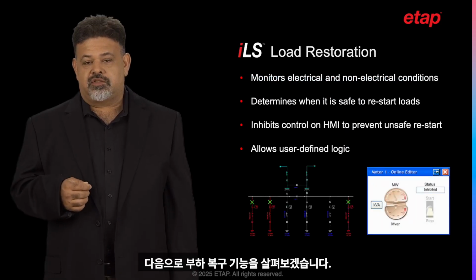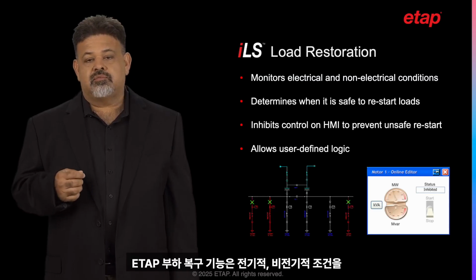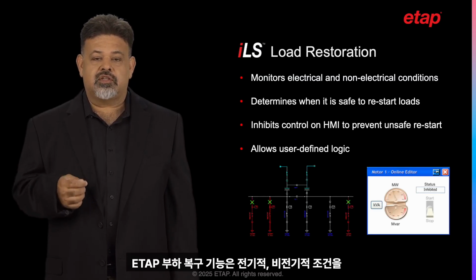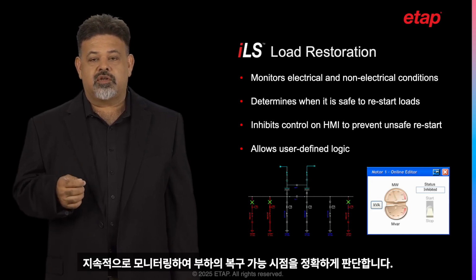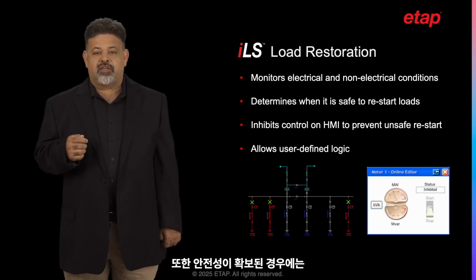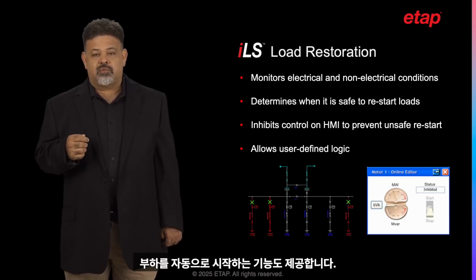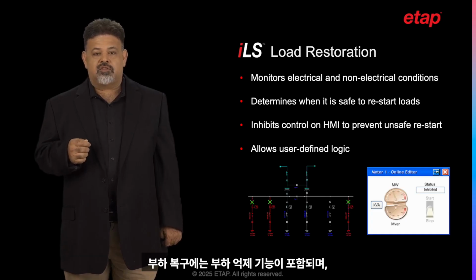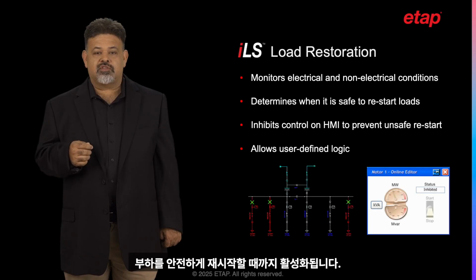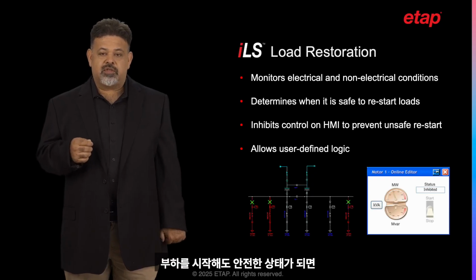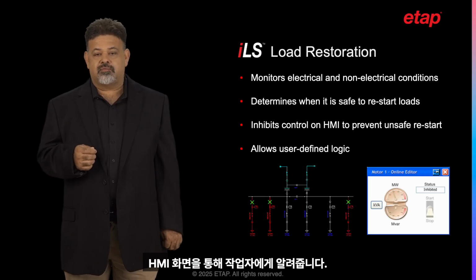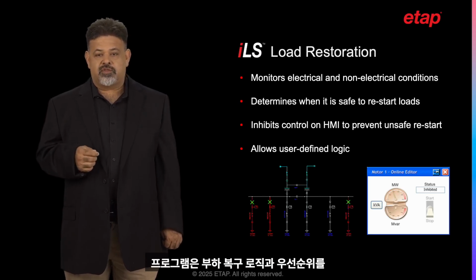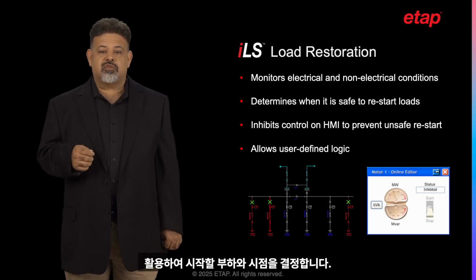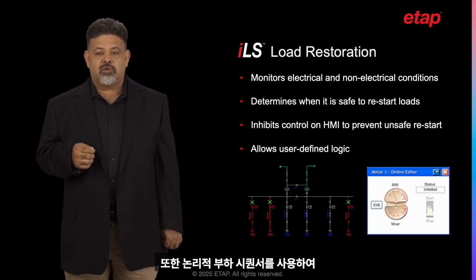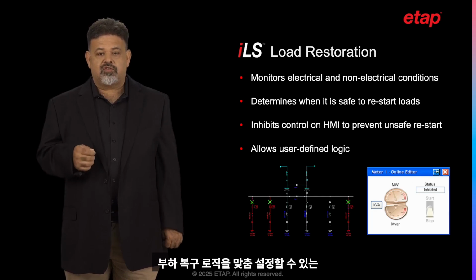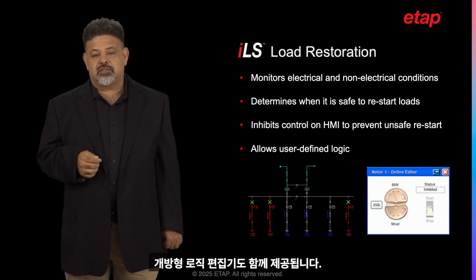Now let's look at the load restoration. ETAP's load restoration monitors electrical and non-electrical conditions to determine when loads can be restored and when they cannot. It also has the capability of automatically starting loads when safety permits it. Load restoration comes with load inhibition, which becomes active until loads can be restarted safely. The HMI screens will indicate to the operator when it is safe to start the load. The program utilizes load restoration logic and priorities to determine which loads can be started and when. It uses a logical load sequencer to restart the process. It also has an open logic editor for customizing the logic.